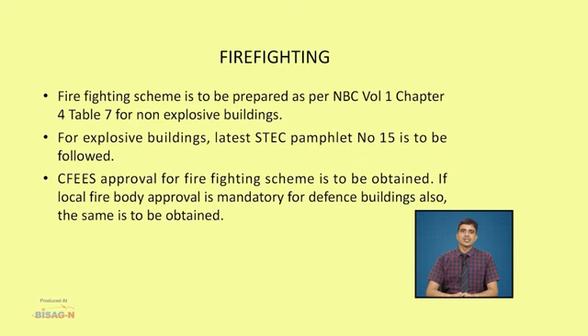Now let's talk about firefighting. The firefighting scheme is to be prepared as per NBC Volume 1, Chapter 4, Table 7 for non-explosive buildings. For explosive buildings, the latest version of STEC pamphlet number 15 is to be followed. CFEES approval for the firefighting scheme is to be obtained. If local fire body approval is mandatory for defense buildings also, the same is to be obtained.